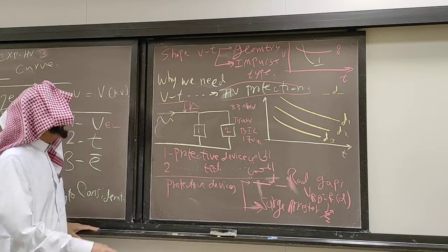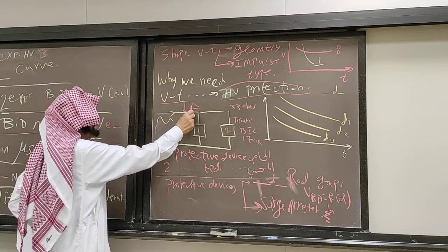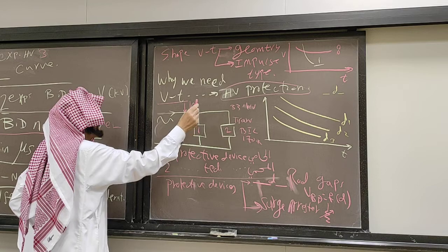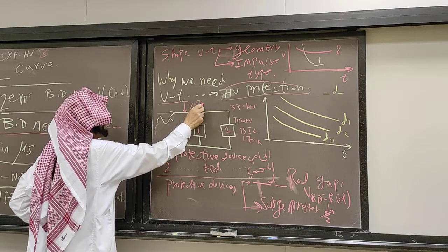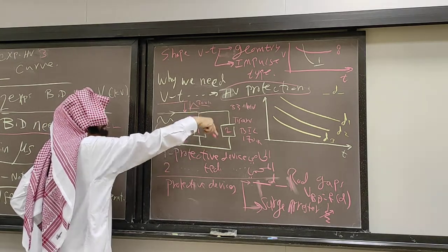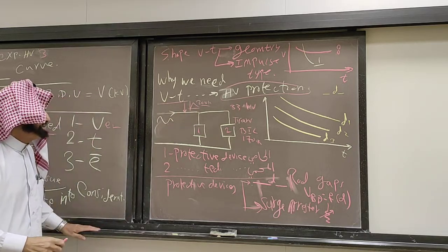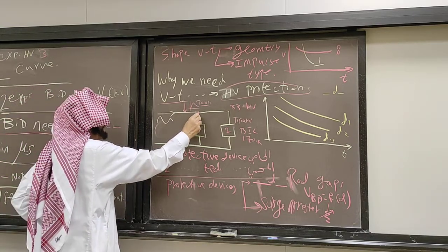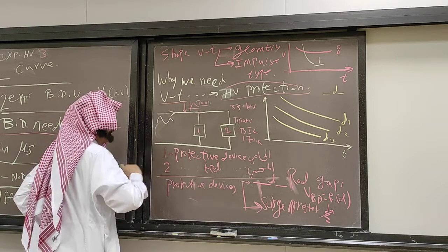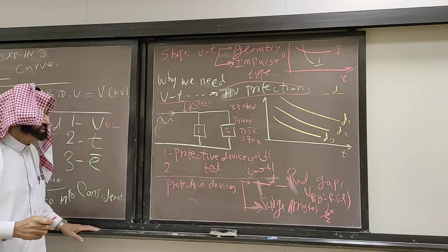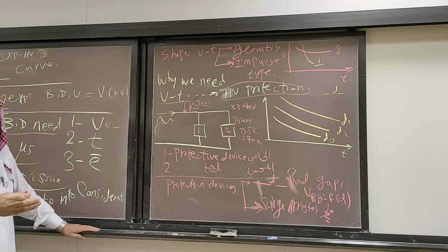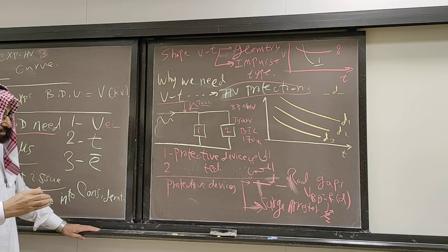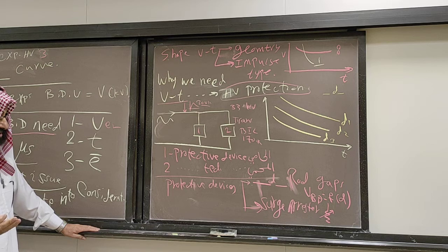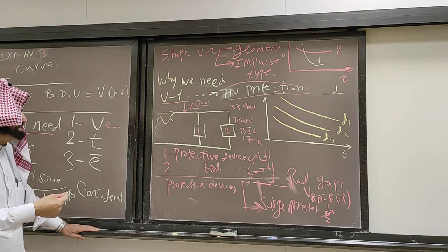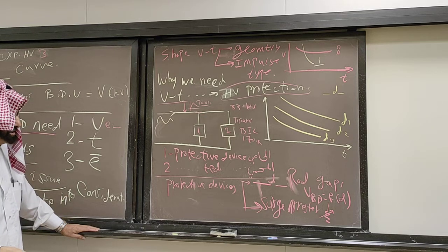But assume that this is an AC system and there is an impulse coming, for example, 300. If it comes to the transformer, it will damage it. So you will put a protection device in parallel with it. As you study in 340, high voltage protection, you put it in parallel. Current protection, you make it in series. This is the difference. There are two differences between current protection and voltage protection.